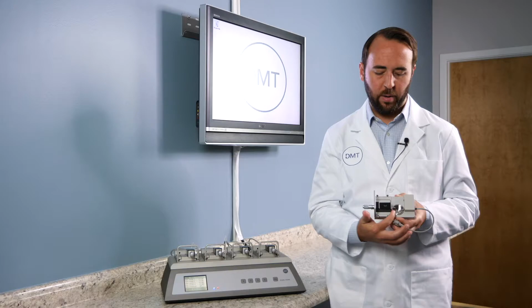One mount is attached to a micropositioner or a micrometer. This is the side that moves. The second side is attached to a force transducer, which is very sensitive and you must be very careful when using this side. The force transducer housing is connected to a transducer cable, which will connect to your interface. There are also 4 screws. These are used for fine adjustments when using resistance vessels.